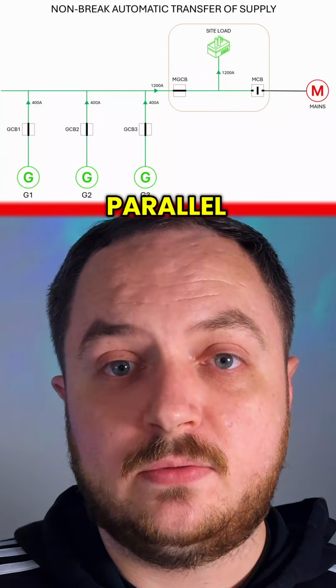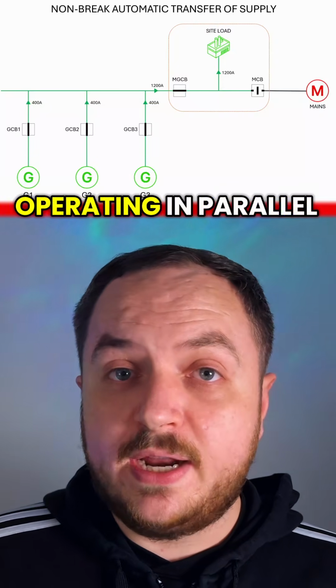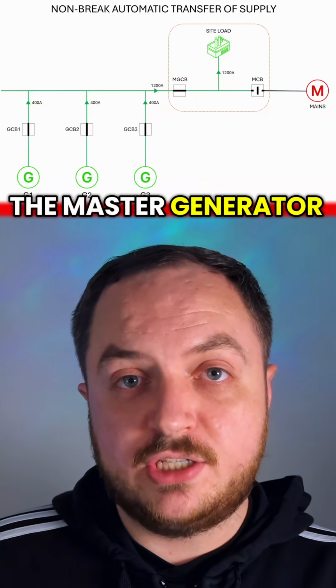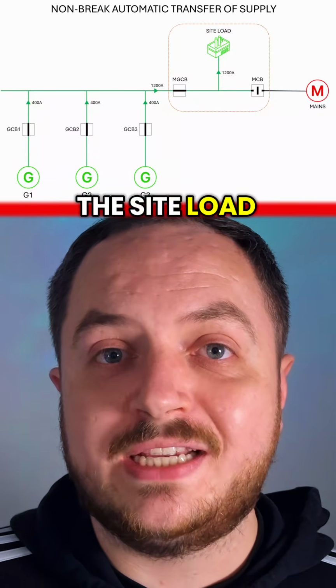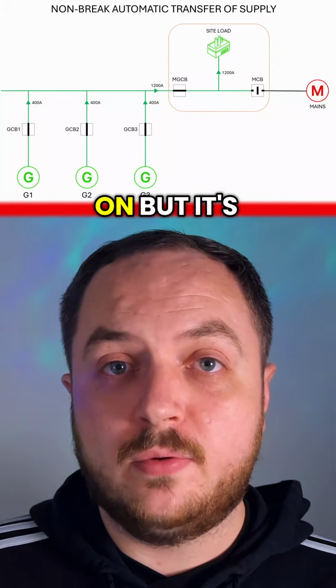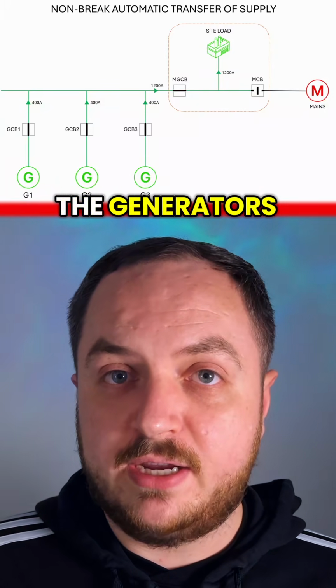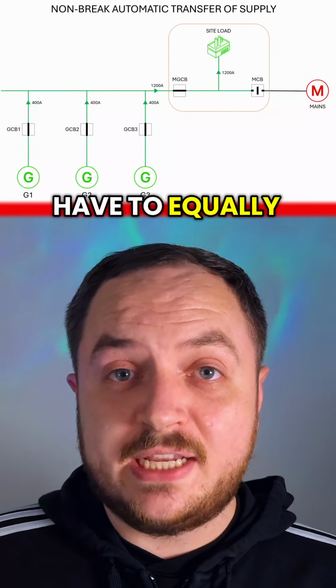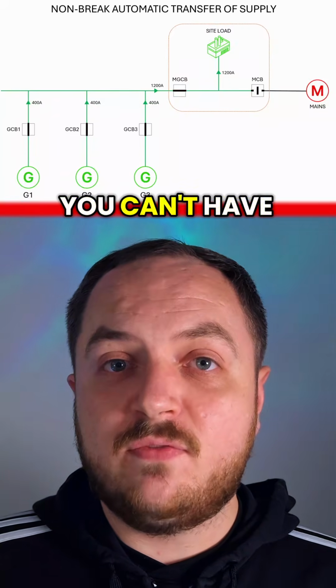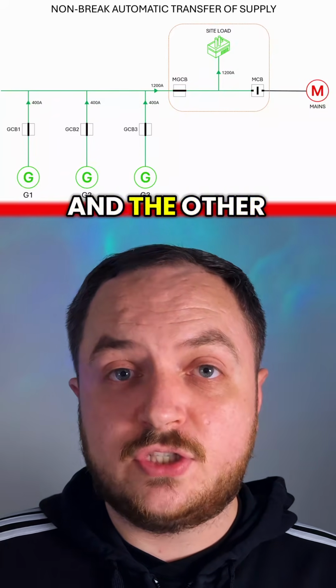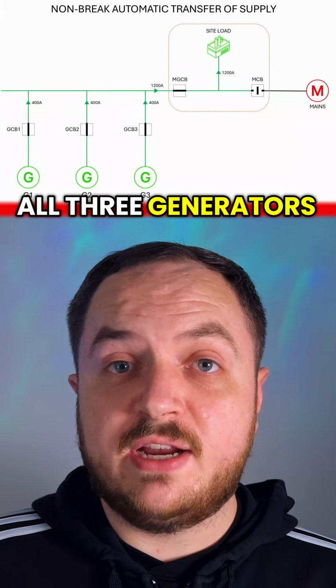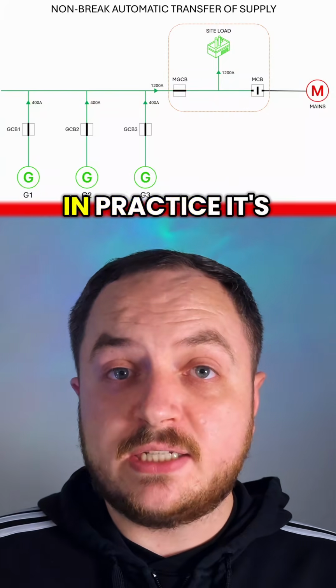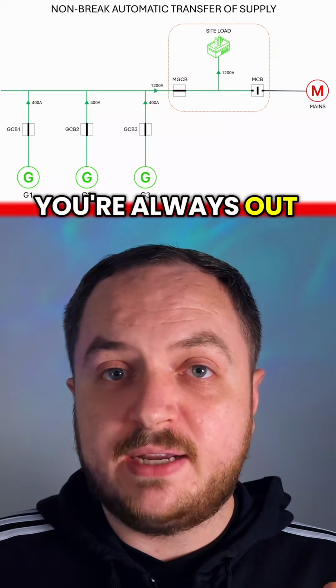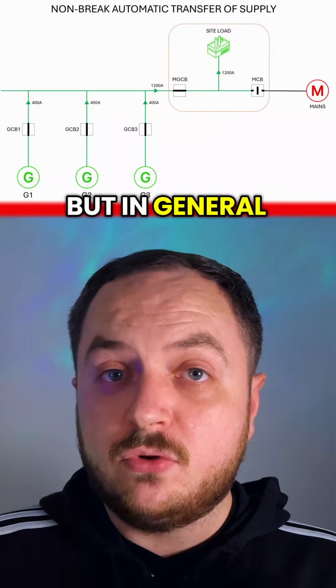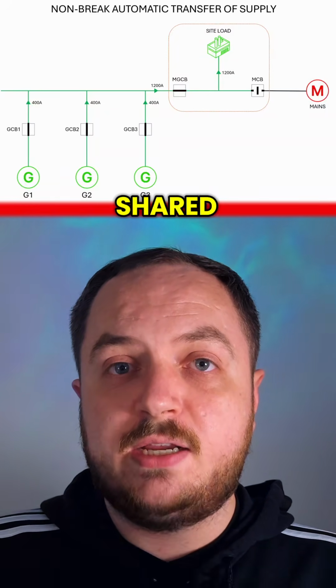Okay, so once those generators get into sync, they close their breaker, and then all three generators are operating in parallel. And basically, when those three generators are operating in parallel, we can close the master generator circuit breaker. The site load is now restored, the power's back on, but it's not from the mains, it's now from the generators. The generators then have to equally supply load to the site. You can't have one generator supplying all the load and the other two basically at no load. All three generators have to share the load equally. In practice, it's never perfect, you're always out by a few kilowatts or so, but in general they're pretty equal and the load is shared equally amongst them.